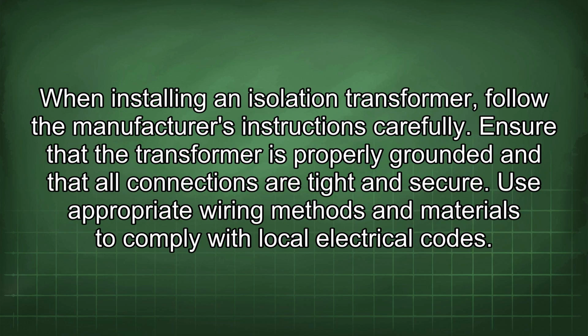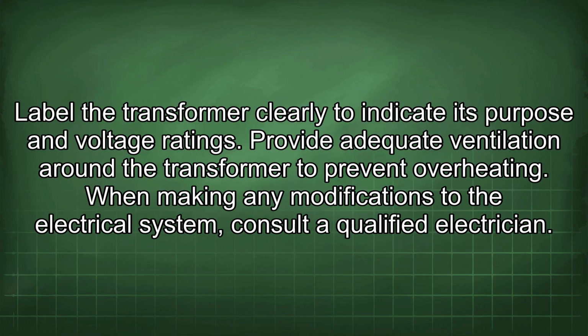When installing an isolation transformer, follow the manufacturer's instructions carefully. Ensure that the transformer is properly grounded and that all connections are tight and secure. Use appropriate wiring methods and materials to comply with local electrical codes. Label the transformer clearly to indicate its purpose and voltage ratings. Provide adequate ventilation around the transformer to prevent overheating.